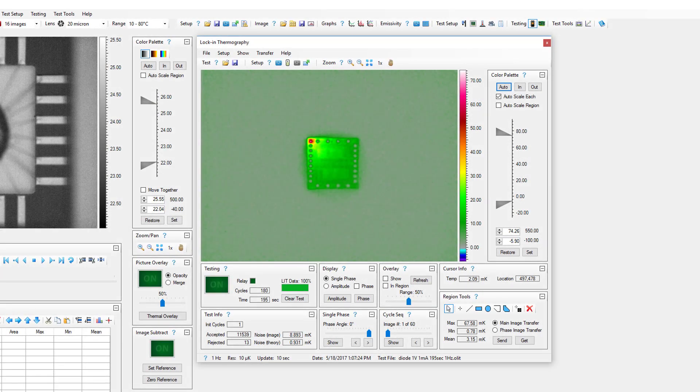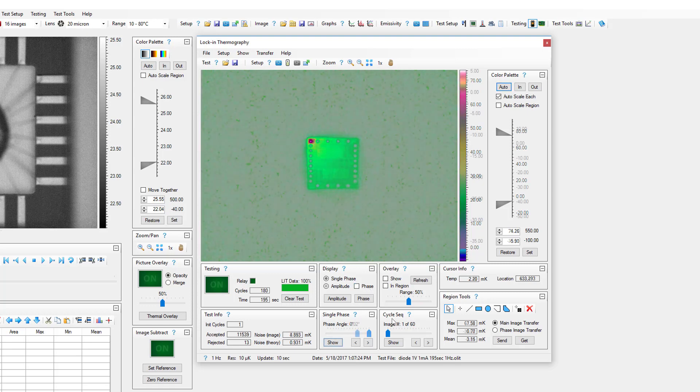There are several different test images that can be used to present the results of a lock-in thermography test: single phase images, amplitude images, phase images, and cycle sequence images.